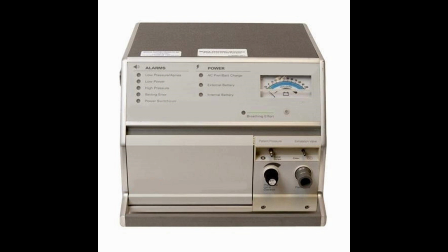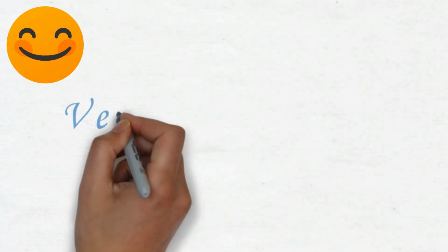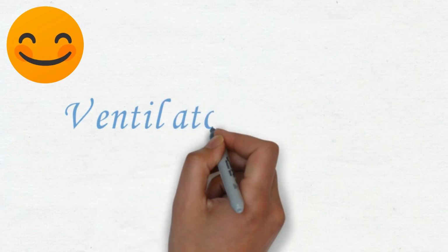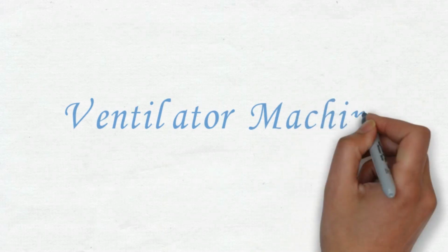Most ventilators with a self-test option have two self-check modes, where one is the short self-test, that is SST, and the other is the extended self-test, that is EST. So that was all the basics about the ventilator machine. I have tried to cover all basic topics which were mandatory to be known by an individual while using a ventilator machine.